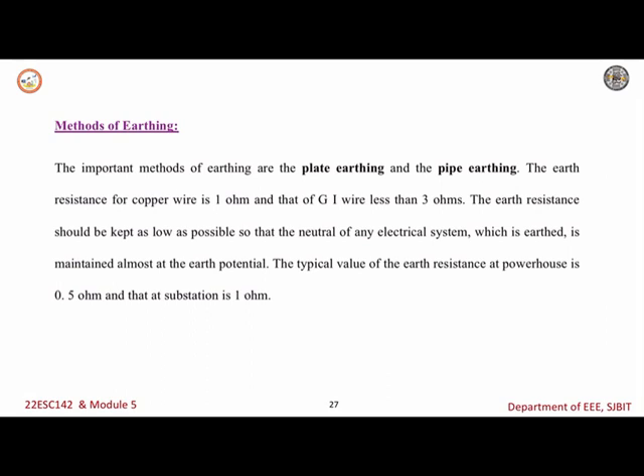At powerhouses, the earth resistance should be around 0.5 ohm, and at substations it should be around 1 ohm, because at the powerhouse we generate power at a very large rating and the current flowing is very high. That's why we maintain the earth resistance at 0.5 ohm there, and near the substation at around 1 ohm.